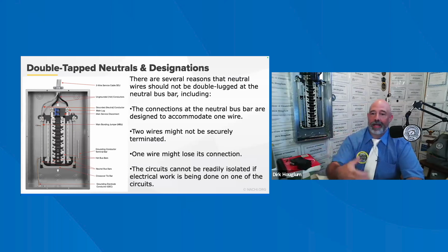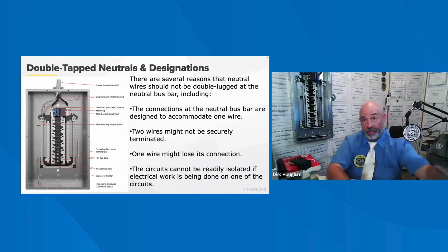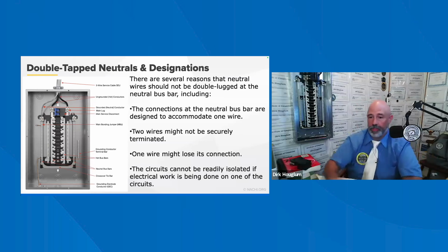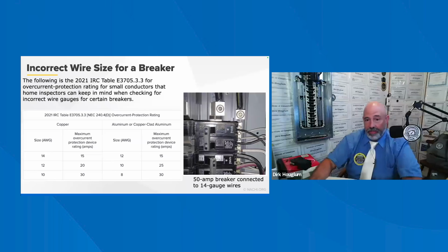A white wire cannot be terminated or connected to a breaker unless it's permanently marked. So a lot of times you use black tape. Works pretty good. Or you take a black permanent marker. Those things can really save your life, especially if you're working in panel boards and electrical. Looking at the table here, we see the 12 gauge wire is a minimum size for a 20 amp breaker. The wire gauge is permitted to be bigger than a 12 gauge when connected to a 20 amp breaker. A 10 gauge wire is the minimum for a 30 amp breaker.